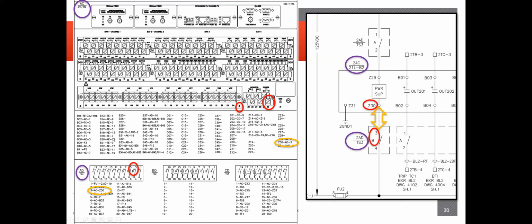This can get a little confusing if you're going down a pretty large rabbit hole of troubleshooting, but all in all, you just have to associate the contacts from the relay to where they're going. In our case here, we have the Z30 contact, and that should be going to B3. If we go down to B3, we can see that it is in fact going back up to the AC identifier here, Z30.